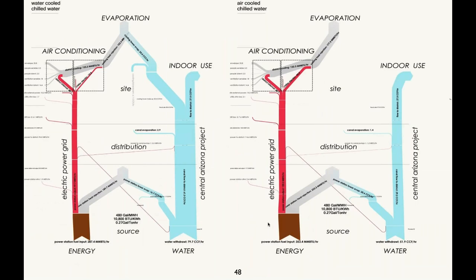If you hit this again, this is an alternative, which would be an air-cooled system. Interestingly, I always assumed as a mechanical engineer that a water-cooled central plant is going to be so much more efficient than an air-cooled system that it always makes sense to do it. And most of the time, it really does.